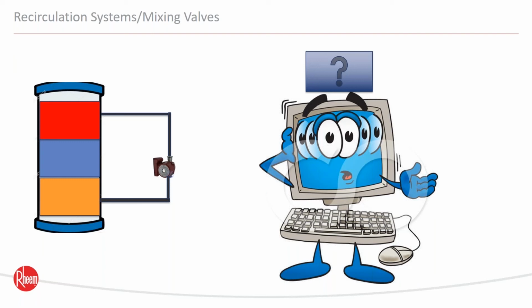Mixing valves, as we talked about, you can increase the capacity of the tank going from 120 degrees, which is what the unit is tested at, up to 140 degrees. It sounds a little counterintuitive, but if you increase the tank temperature, the unit will run more efficiently, especially if there are times of the day that the element is kicking on. It's allowing the heat pump to do more of the recovering instead of that element. So you can maximize efficiency by ramping up the temperature. Again, if you're going to set it above 120 degrees, I would not recommend having the customer do that.